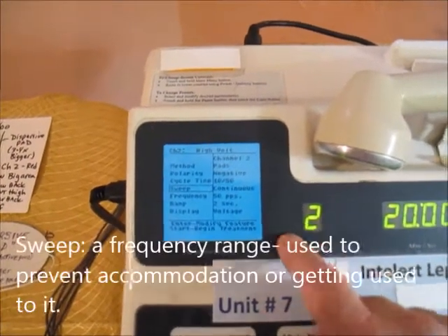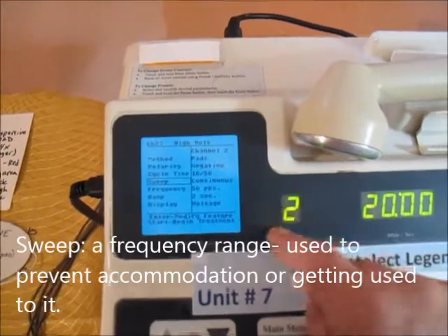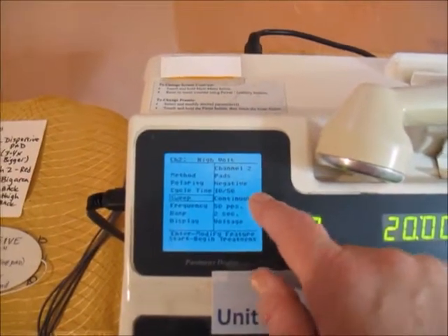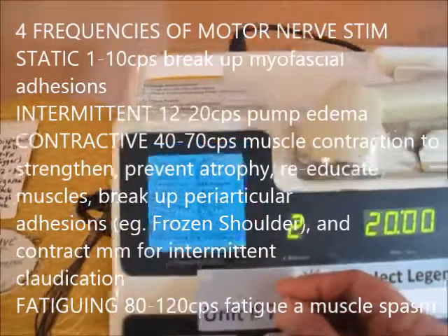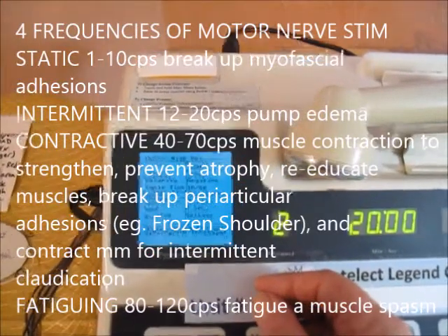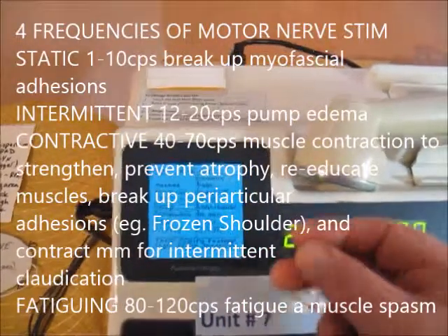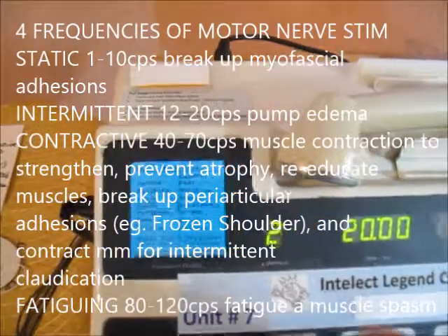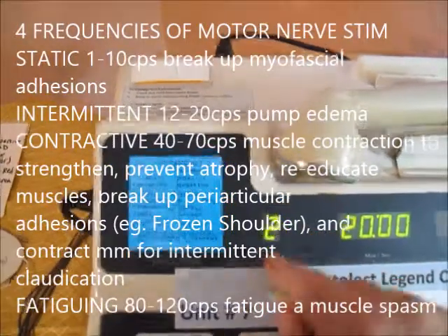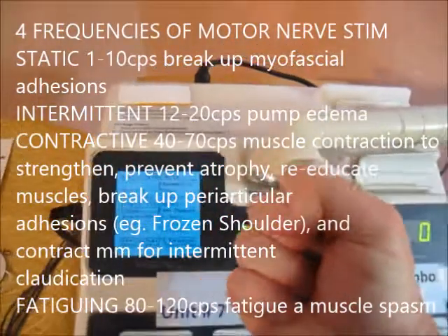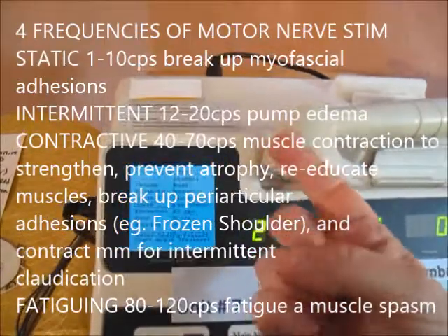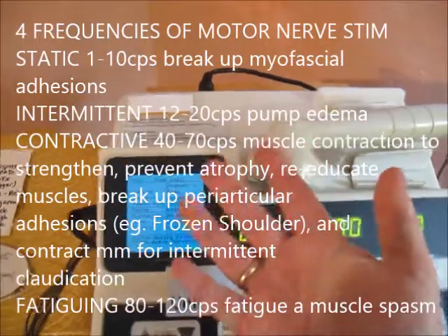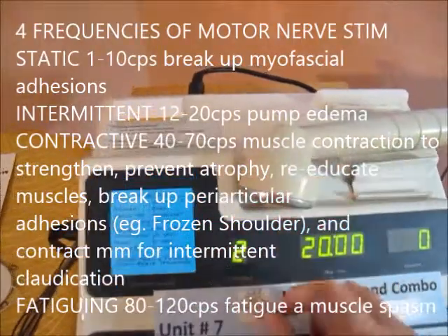Sweep allows us to go through a frequency range. Frequency ranges are beneficial because if you always stimulate at one single frequency, the body gets used to it. To prevent accommodation, we use a sweep covering the full available range. For myofascial adhesions using static frequency, we use 1 to 10 cycles per second. For a pumping effect to reduce edema — intermittent motor nerve stim — we set it from 12 to 20 cycles per second. For contractive to strengthen muscles, prevent atrophy, do muscle re-education, break periarticular adhesions like frozen shoulder, or pump the legs for intermittent claudication, we use 40 to 70 cycles per second.